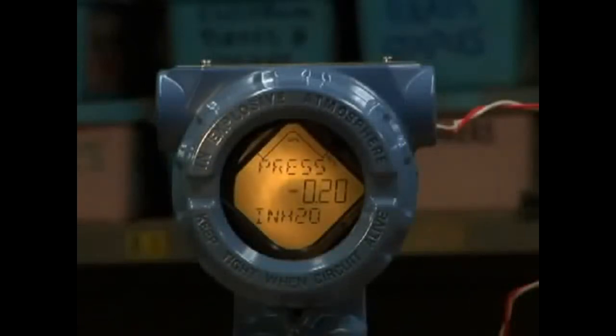Right now with nothing flowing we're getting a reading which is effectively zero. But let's turn the water flow on and see what happens. So it jumps to just over, right about 18 inches of water with the flow what it is.